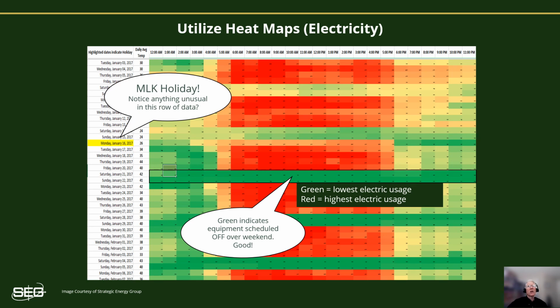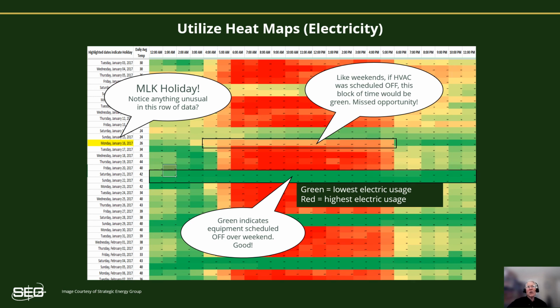You can see here Monday, January 16th, that's Martin Luther King Jr. Day, and the building was unoccupied for the holiday. Yet it's still showing red, which means considerable consumption was happening all day. It's most likely that the HVAC wasn't scheduled off to capture the savings available over the holiday.